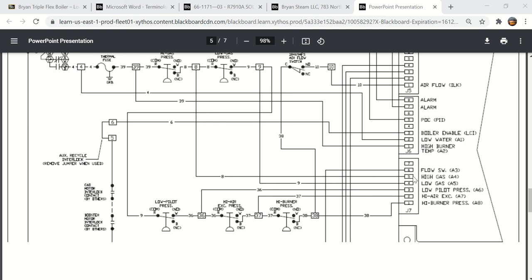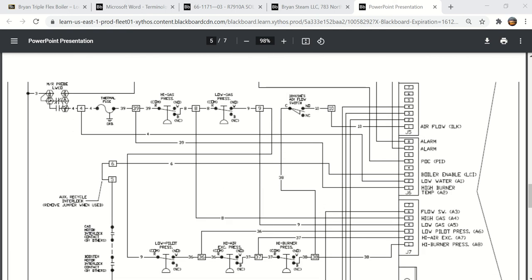And this is kind of important. You may wonder why there's no wire hooked up on the alarm terminal. Wouldn't you want to know when the low water cutoff is an alarm? Obviously you would. There's a red LED on the low water cutoff, but with the door closed, you're not going to be able to see that. So how would you know that it's an alarm? Well, through the inputs, and that's what you're looking at here on J6 and J7 of the controller. Through these inputs, it can monitor whether or not a device up here, thermal fuse, as we follow through, you'll see it can actually monitor that and give you the information on the touchscreen display whether that device is in alarm or if it's still in its normal state.